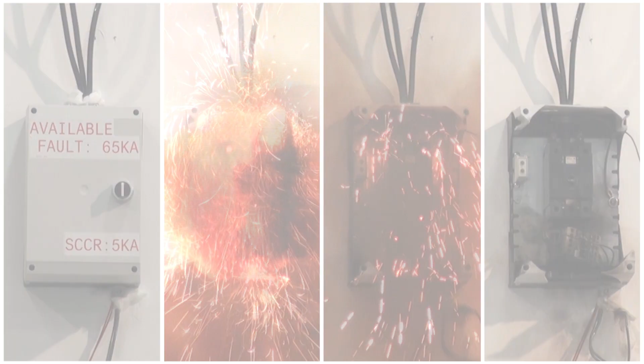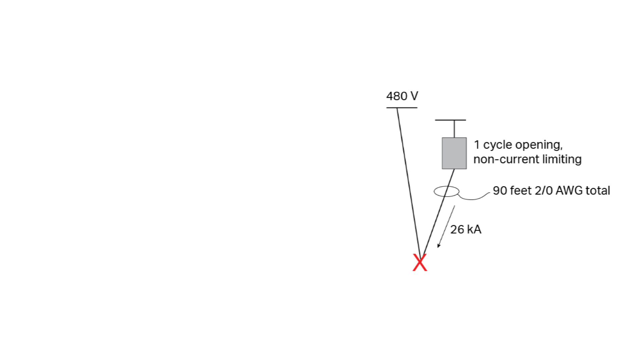The cable whip test visually illustrates the difference between current limiting and non-current limiting overcurrent protective devices. These tests were conducted at 480 volts with 90 feet of 2/0 conductor placed on the lab floor. The available fault current is calibrated to 26,000 amps symmetrical. The first test uses a non-current limiting protective device with a 1-cycle clearing time.